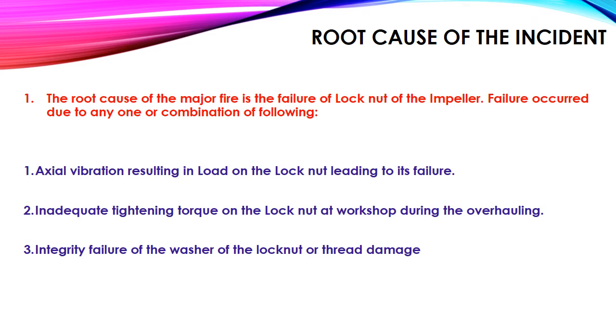The root cause of the major fire is the failure of the lock nut of the impeller. Failure occurred due to any one or a combination of the following: axial vibration resulting in load on the lock nut leading to its failure, inadequate tightening torque on the lock nut at the workshop during the overhauling, integrity failure of the washer of the lock nut, or thread damage.